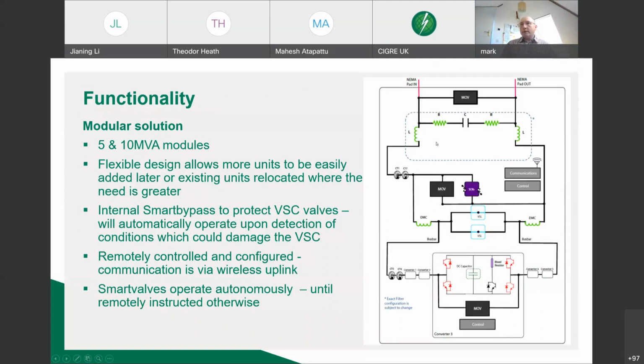But in parallel with this, and this is the crux of how these devices look after themselves, is what's called a fast bypass. It has a combination of power electronics, in terms of silicon controlled rectifiers, to provide very fast actuation, and then vacuum switches, which provide the mechanical and rating capability, so that we get the high fault currents, the high duties that these will need to see under fault, and the power electronics are protected.